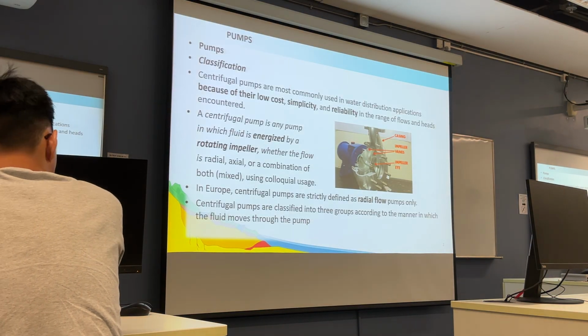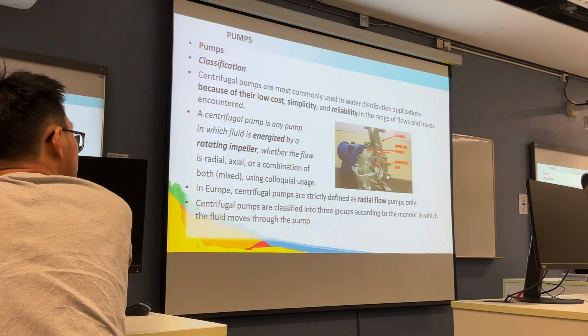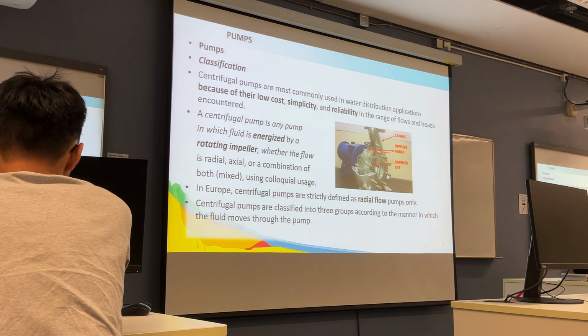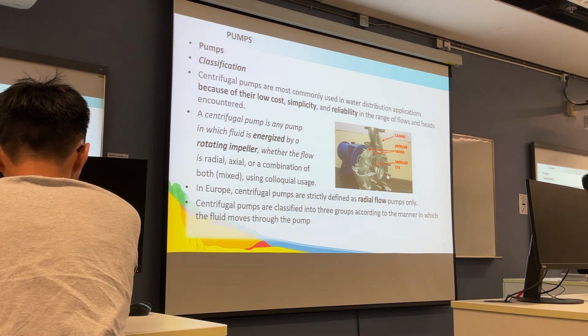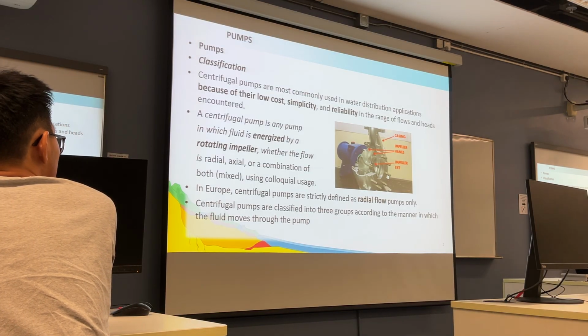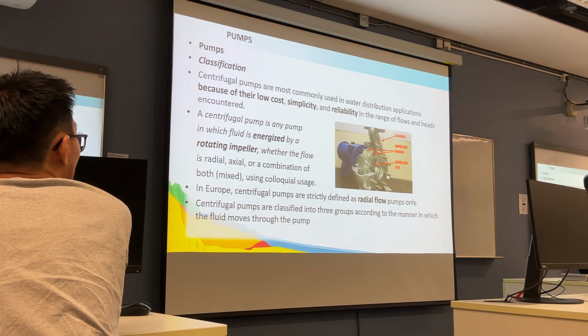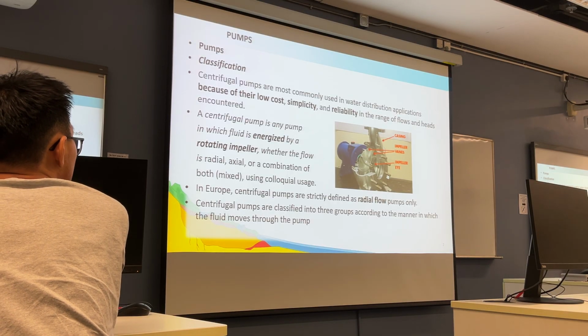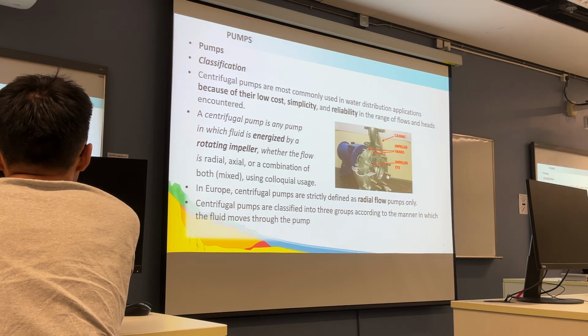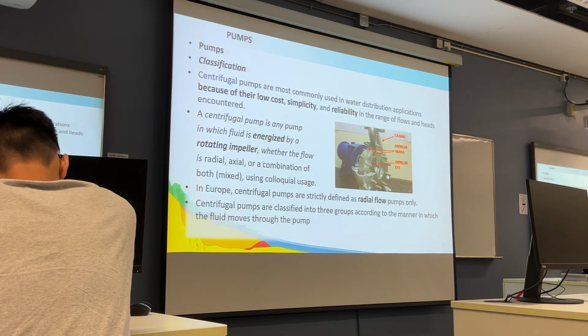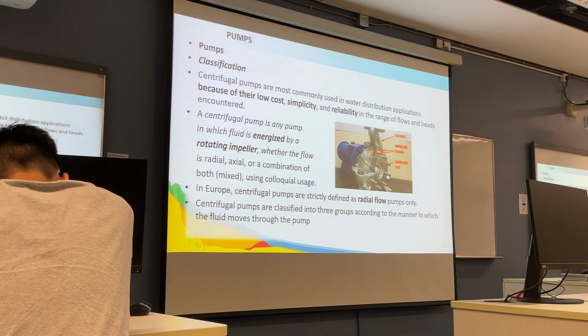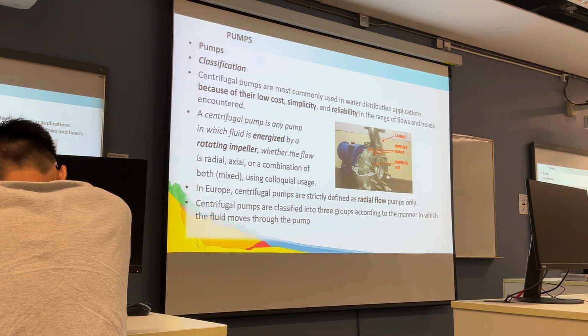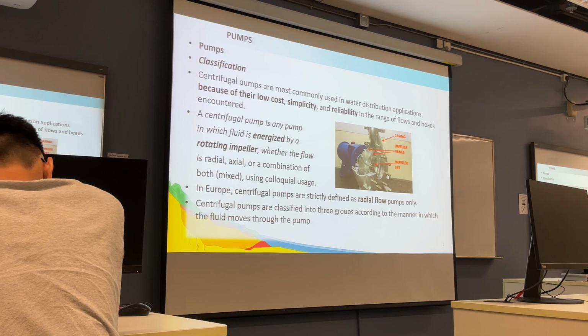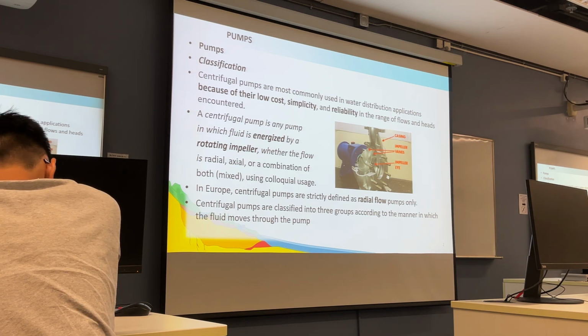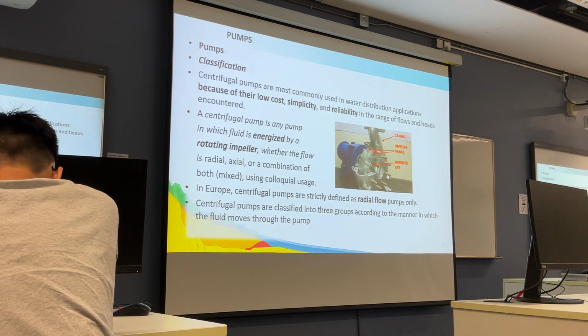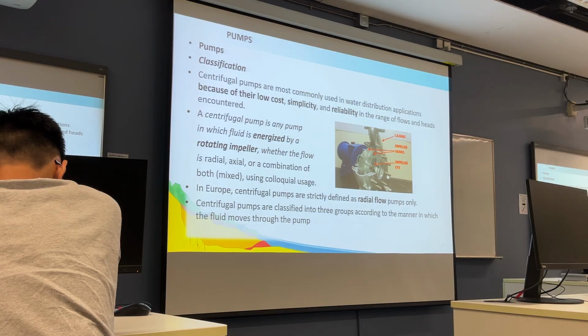So for the manufacturers, kinds of consideration, you may need to determine how large the size of the impeller is. Okay, you may consider the rotational speed of the impeller, and also you may consider the design of the flow. Okay, so this will affect the efficiency. We call it the efficiency of the pump. Okay, so the efficiency of the pump is talking about how much of the energy input can be reflected as output to the water flow. Right.